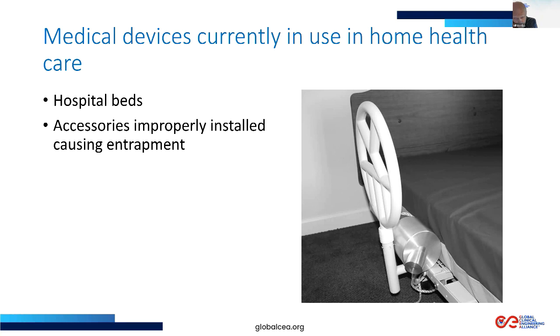In this case, this is quite a large gap. Patients slid off their mattress, their neck got caught in this gap, and they died. The problem here was not the device itself, but the fact that it was installed by someone who didn't understand the hazards of creating these large gaps. If they'd installed it properly, this incident would not have happened. Next slide, please.